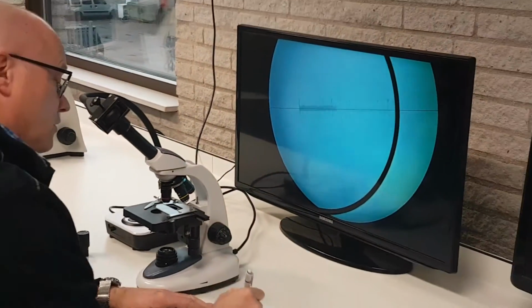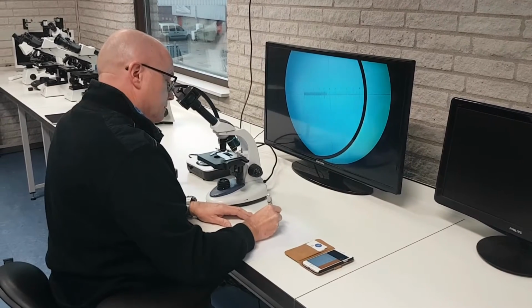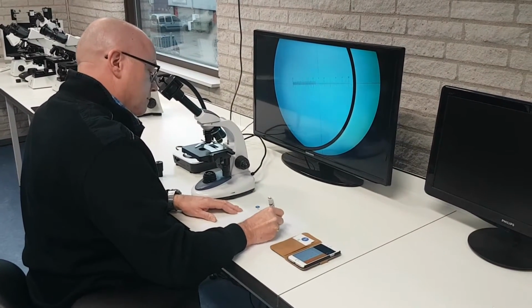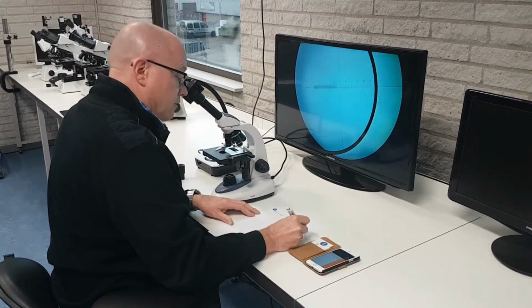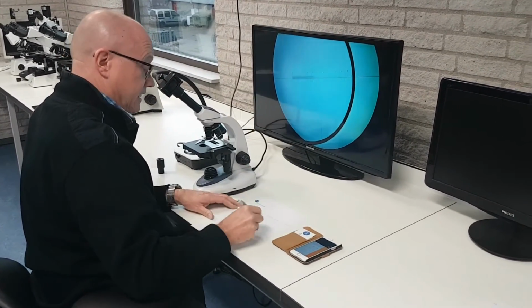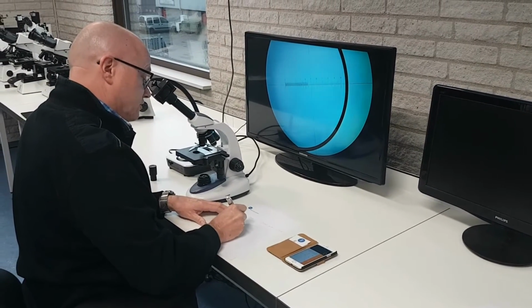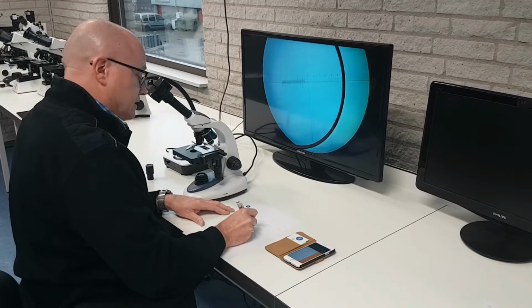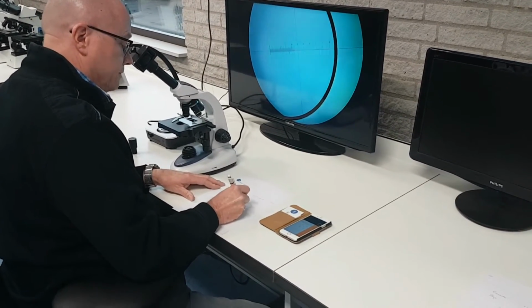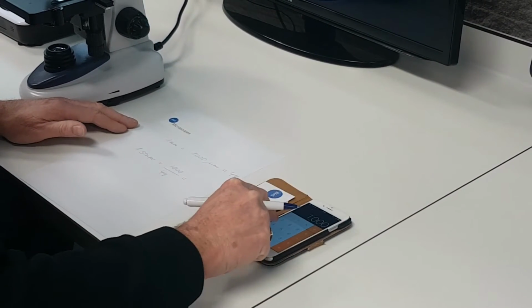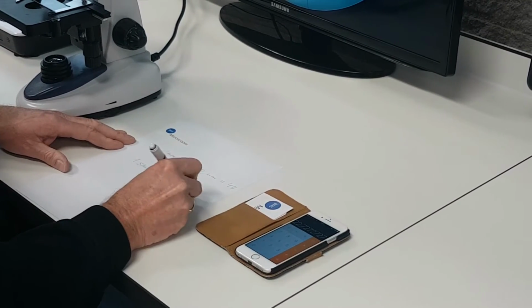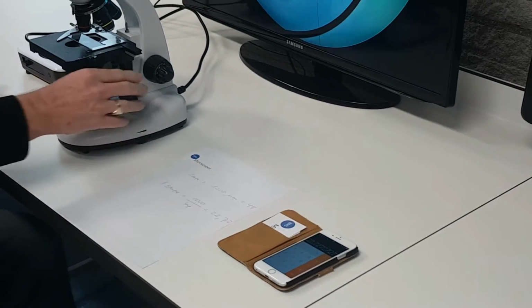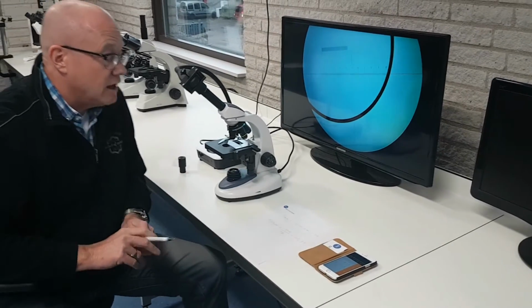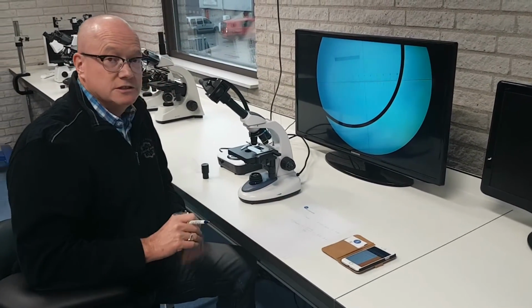That means 1 millimeter, which is 1,000 micrometers, equalizes 44 stripes in the reticule. That means that one stripe equalizes 1,000 divided by 44. Use your calculator: 1,000 divided by 44 is 22.72 micrometers. That means that one stripe in the eyepiece reticule equalizes 22.72 micrometers.